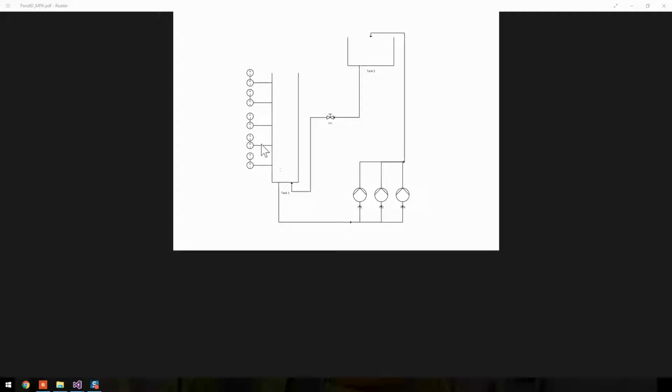In this video we'll make some logic to detect if any of the sensors are faulty. The way we're going to detect that is if sensor 2, for example, is active, sensor 1 should also be. Since if the water level is above here, it's definitely above here as well, unless there's a fault on the sensor. So if a sensor is true, the sensor below it has to be true as well.